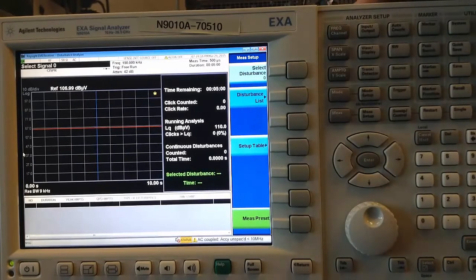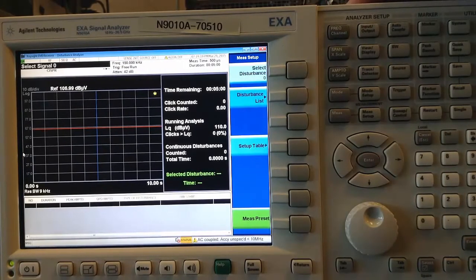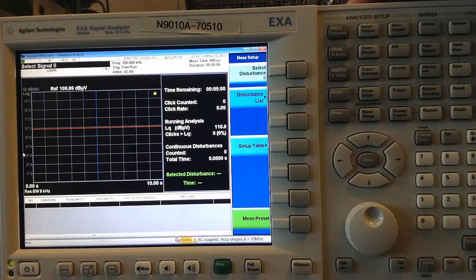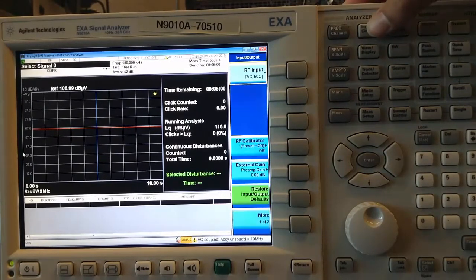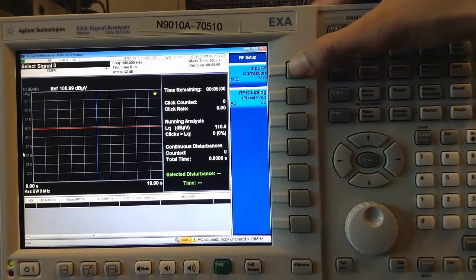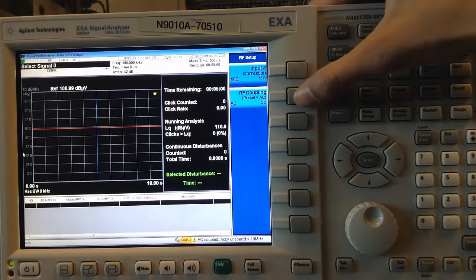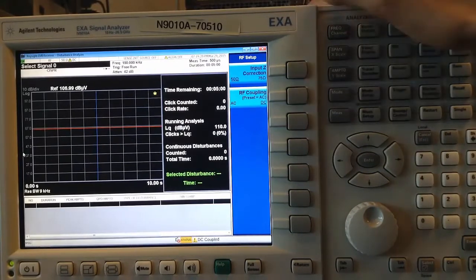The next step is to change the input coupling to get better accuracy at frequencies less than 10 MHz. To do this, I press Input-Output, go to RF Input, and switch the RF coupling to DC.